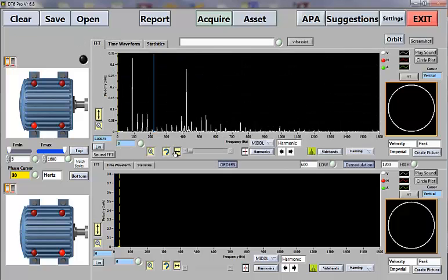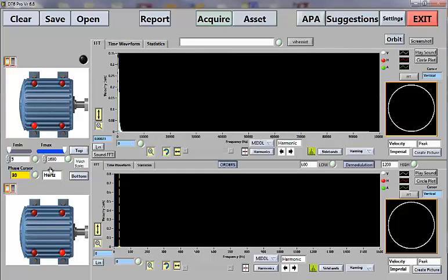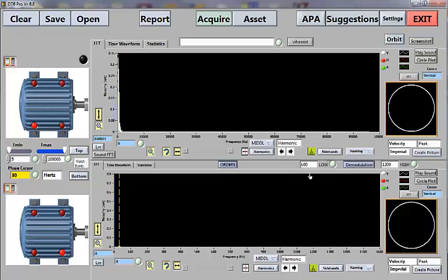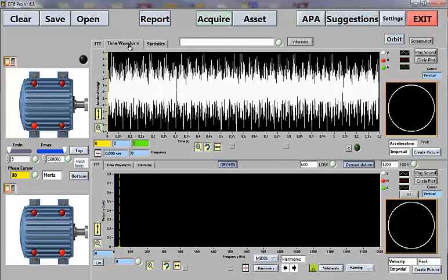But we can just look at it and see, in this case, that this sensor is an ultrasound sensor that was measuring up to 96,000 hertz. So we can change the filter to match that, and then we can look at all of the vibration we have from that wave file just as we normally would.